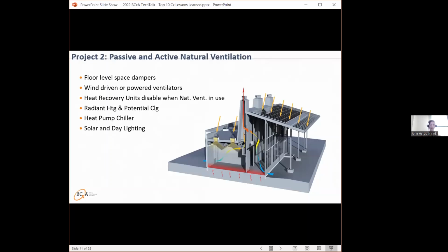You might run into these projects, whether it's net zero or a school. Typically I see a lot of these where they try to use natural ventilation to the advantage of the classroom environment, whether K through 12 or higher ed. In this project specifically, we had floor level space dampers, radiant slab, wind-driven and powered ventilators at the roof level, and heat recovery units supplying the classrooms that were disabled when natural ventilation was in use.